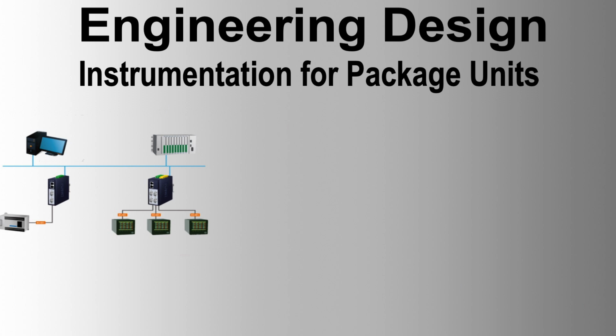Where the equipment package unit control system, or IPS logic solver, makes use of another transmission protocol as a standard, the equipment package vendor shall confirm with the DCS vendor that this particular protocol can be implemented in the plant DCS. The vendor shall further demonstrate that the protocol is industry tested and proven. The principal's approval shall be obtained for the use of such transmission protocols. The contractor shall have the final responsibility of ensuring satisfactory communications with the plant DCS.